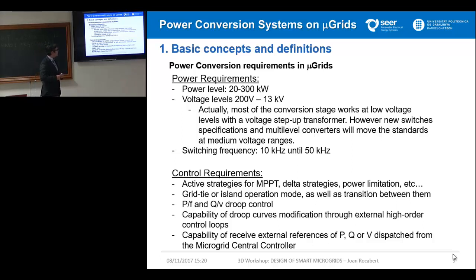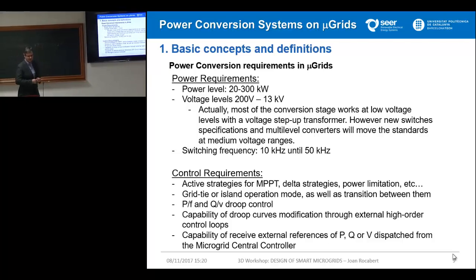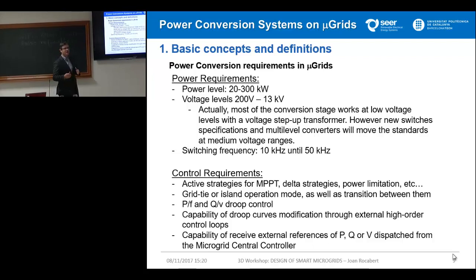The control requirements. Well, the control requirement for the converter will be to allow active strategies for MPPT. We have to allow delta strategies, power limitation. The converter should be able to work in grid-connected or island mode, as well as handle the transition between the different modes. Okay, it should be able to implement droop control, because until now it has been the most standard and fastest solution to maintain the microgrid at its equilibrium point. Okay, at least as the last reserve, and it should also have the capability of modifying those droop curves.